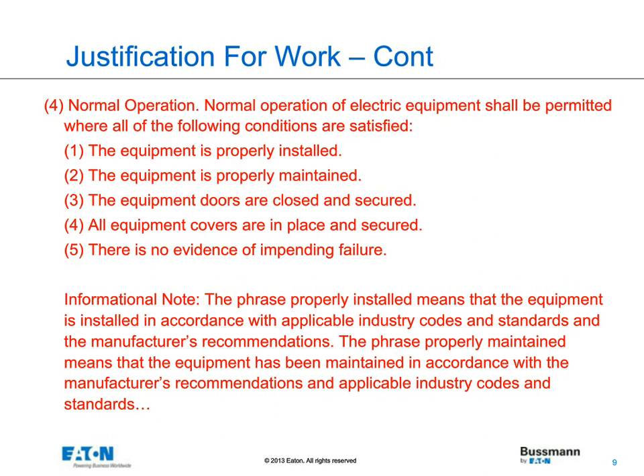The next section talks about the justification for work, and this is something that's new. There's been a real drive to say that in some instances you do not have to have arc flash PPE, if you will, and they decided to put in a condition for that, and we'll see this later on when it comes to the table method we'll talk about later in this presentation. But it talks about normal operation, and under some conditions, if I have what's considered normal operation, and I have these conditions, the equipment's properly installed, it's properly maintained, the doors are closed and secured, and covers are in place, and there's no evidence of impending failure, there might be a condition where doing a certain task, provided those conditions apply, we don't have to wear PPE.